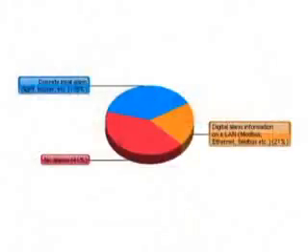Even in the face of heightened personnel danger due to failed circuit breakers and power supplies, 41% of respondents said they had no alarms at all, while 38% said they used local discrete alarms such as a light or a buzzer. Only 20% said they put digital alarm information on a LAN so that responding operators and maintenance personnel can be prepared for danger long before they open that cabinet.